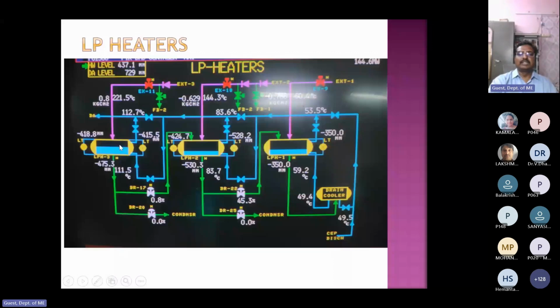Okay. And the steam: this is the extraction. Extraction steam comes to LP heater 3. The condensate is supplied to LP heater 2 because LP heater 3's temperature is more than LP heater 2's. So the condensate is supplied back to LP heater 2. In the same way, the condensate from LP heater 2 is sent back to LP heater 1. From LP heater 1, it is sent back to the drain cooler. From the drain cooler, it is sent to the condenser.